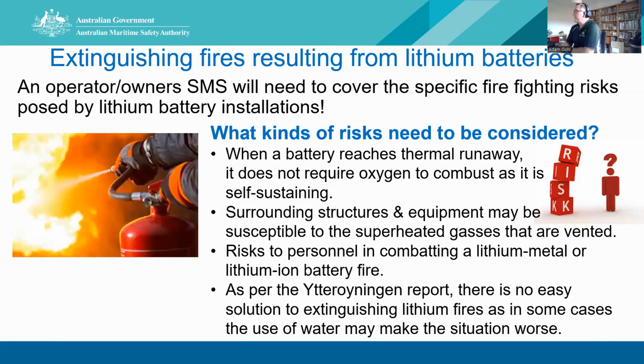Other issues, fighting the fire. We have safety management systems in Australia, so if you have lithium batteries, you need to annotate that there's lithium batteries on board and what you're going to do about it if there is a fire. When a battery reaches thermal runaway, it does not require oxygen to combust. It's self-sustaining, so that makes it, throw it in the water, she'll still burn.